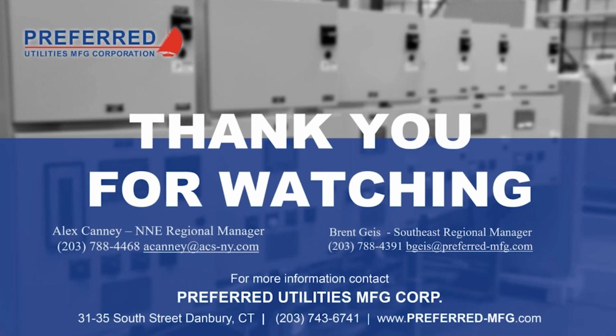When we are using a positive displacement pump skid, we have to do the math, and the pipe sizing and depth, and the amount of fuel that we're moving are all key considerations. Submersible pumps are great at flowing a large quantity of fuel. However, they aren't so great when it comes to head pressure. So if you're trying to pump fuel to a second, third, fourth floor, or a long distance, and you're losing a lot of pressure from the pipe sizing, submersibles may not be the best idea. Positive displacement, you can do hundreds of gallons per hour or per minute at very high pressures. I recently designed a couple projects where we needed about 200 psi, and that's something a submersible pump won't do for you.